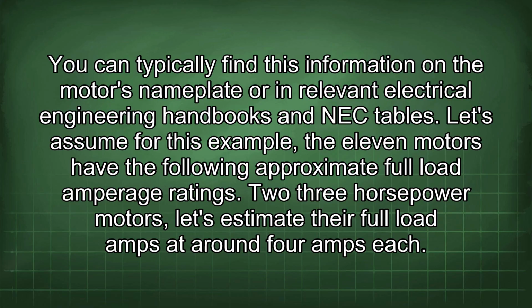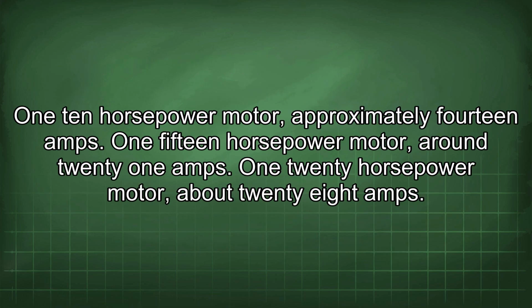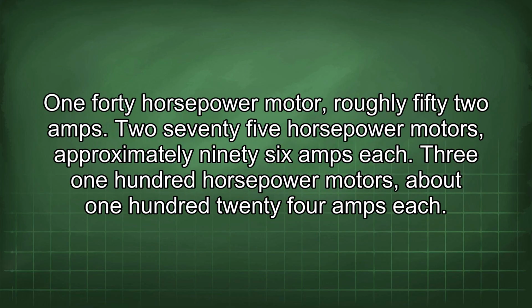2 3 horsepower motors, let's estimate their full load amps at around 4 amps each. 1 10 horsepower motor, approximately 14 amps. 1 15 horsepower motor, around 21 amps. 1 20 horsepower motor, about 28 amps. 1 40 horsepower motor, roughly 52 amps. 2 75 horsepower motors, approximately 96 amps each. 3 100 horsepower motors, about 124 amps each.